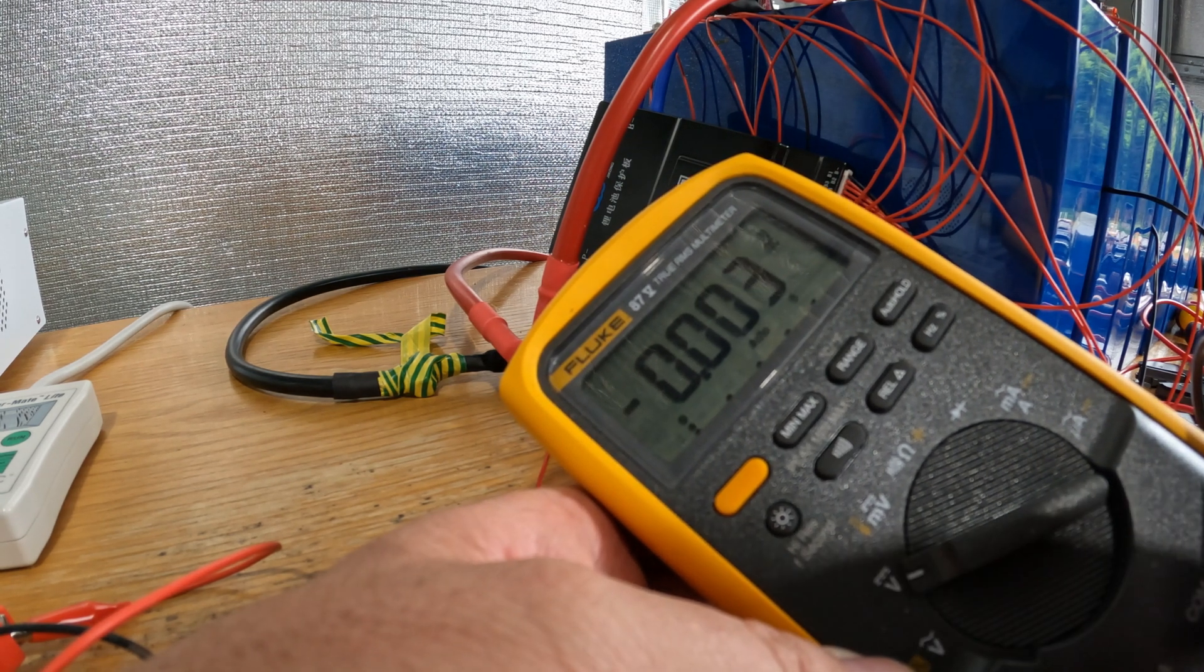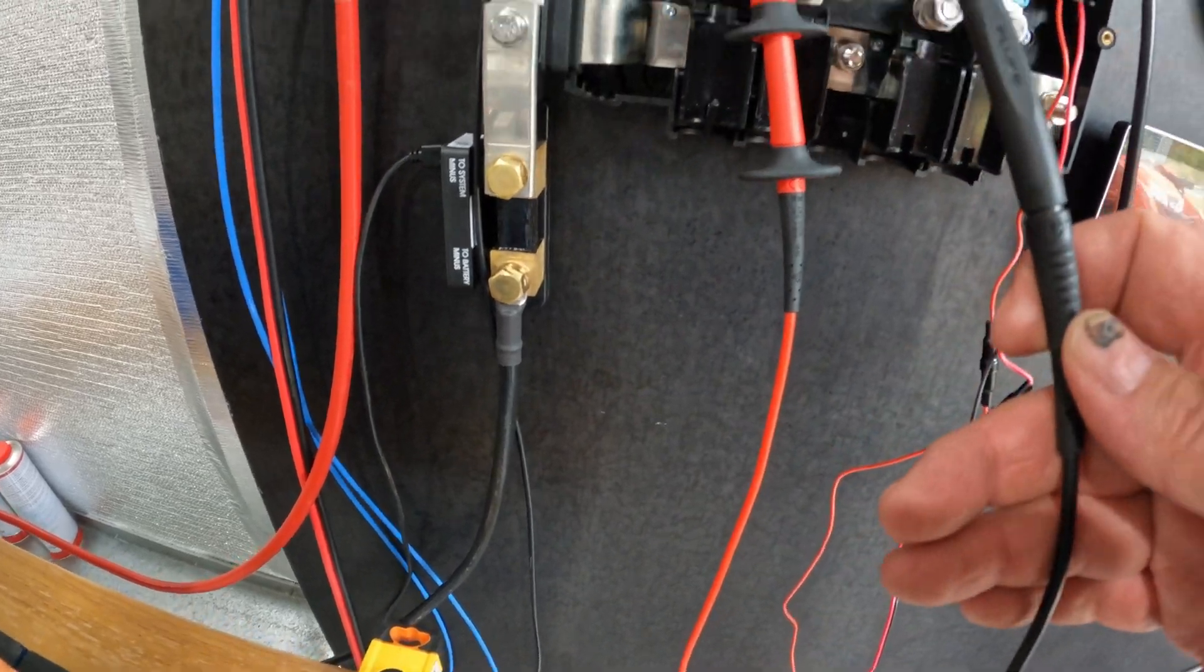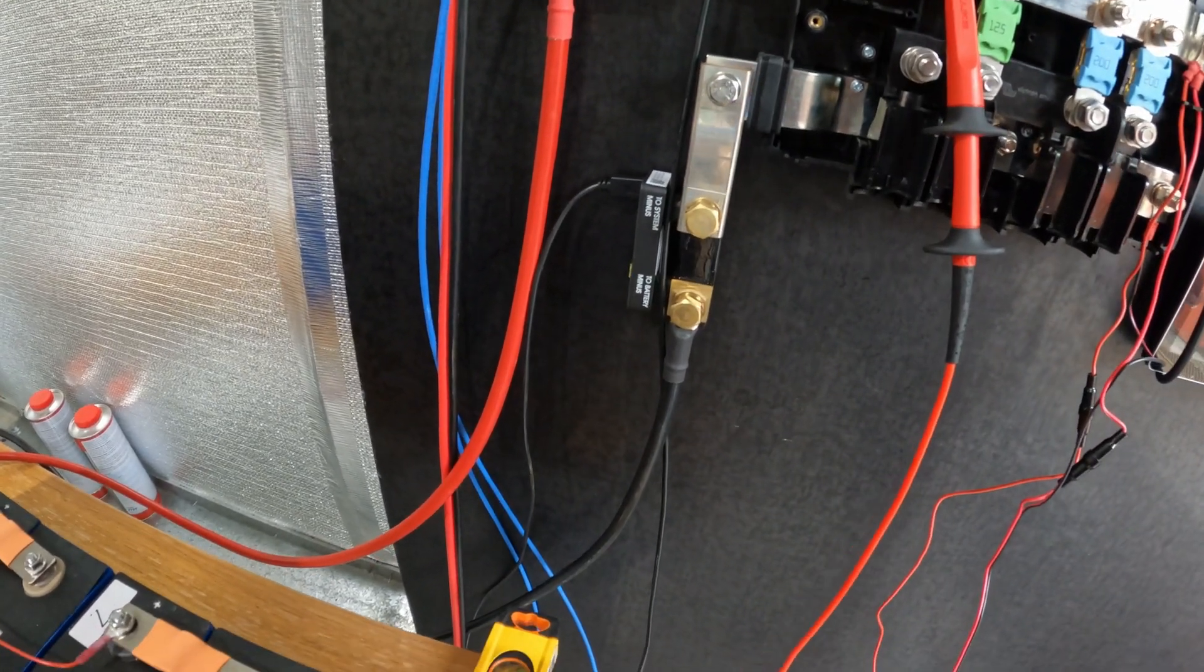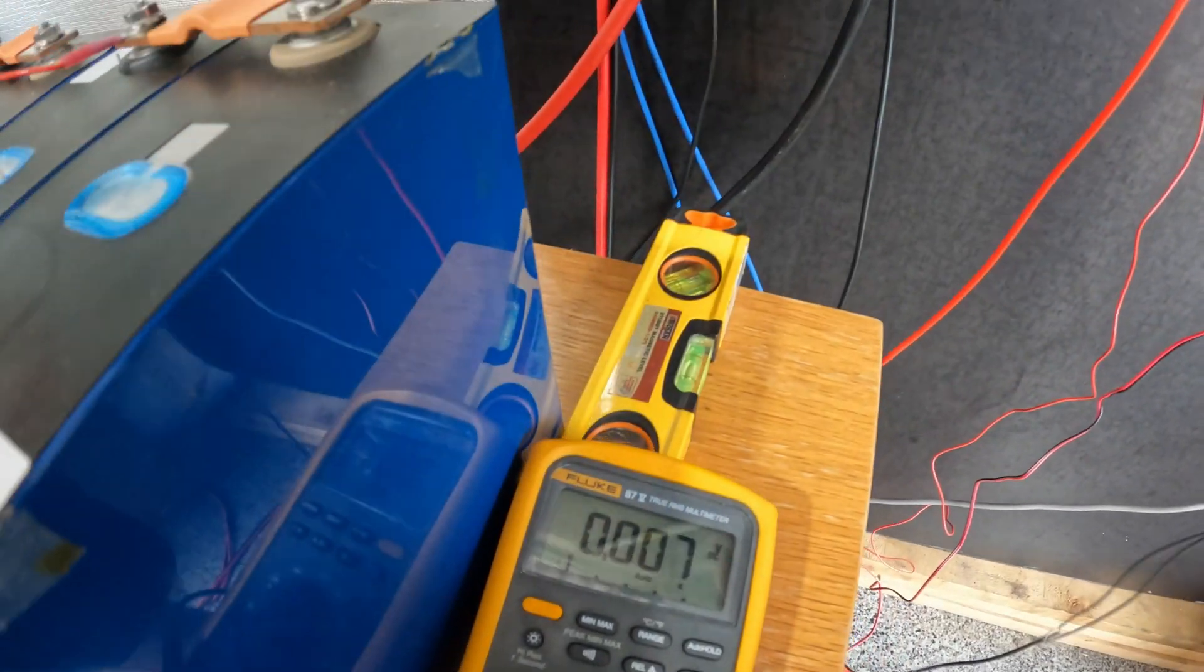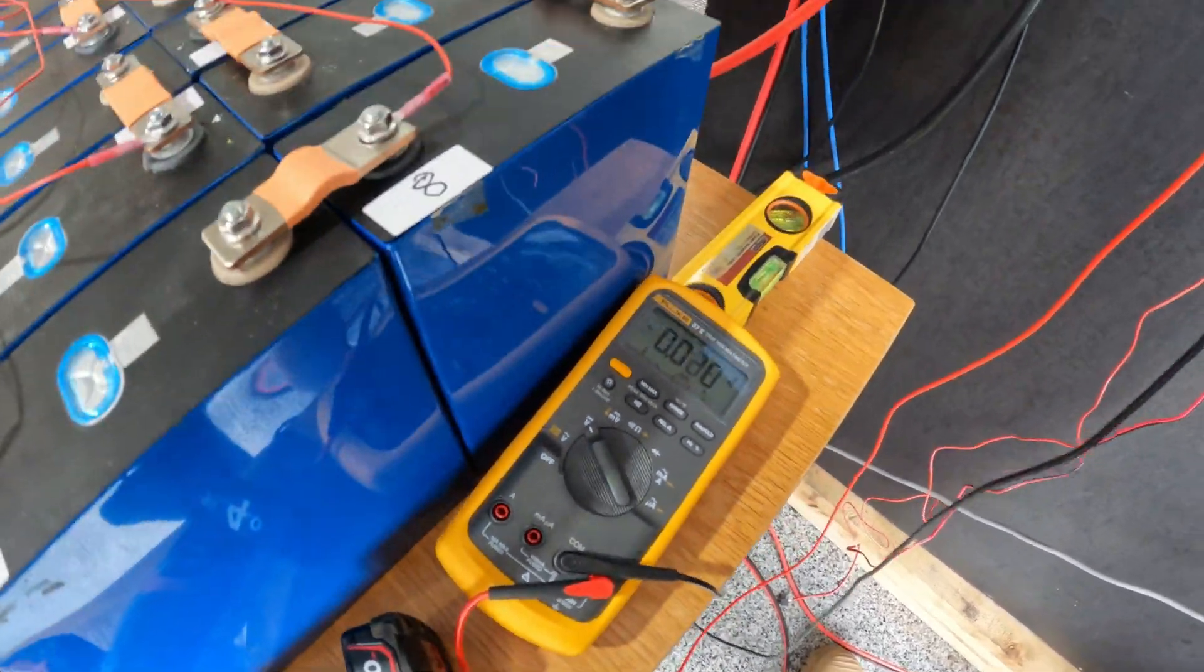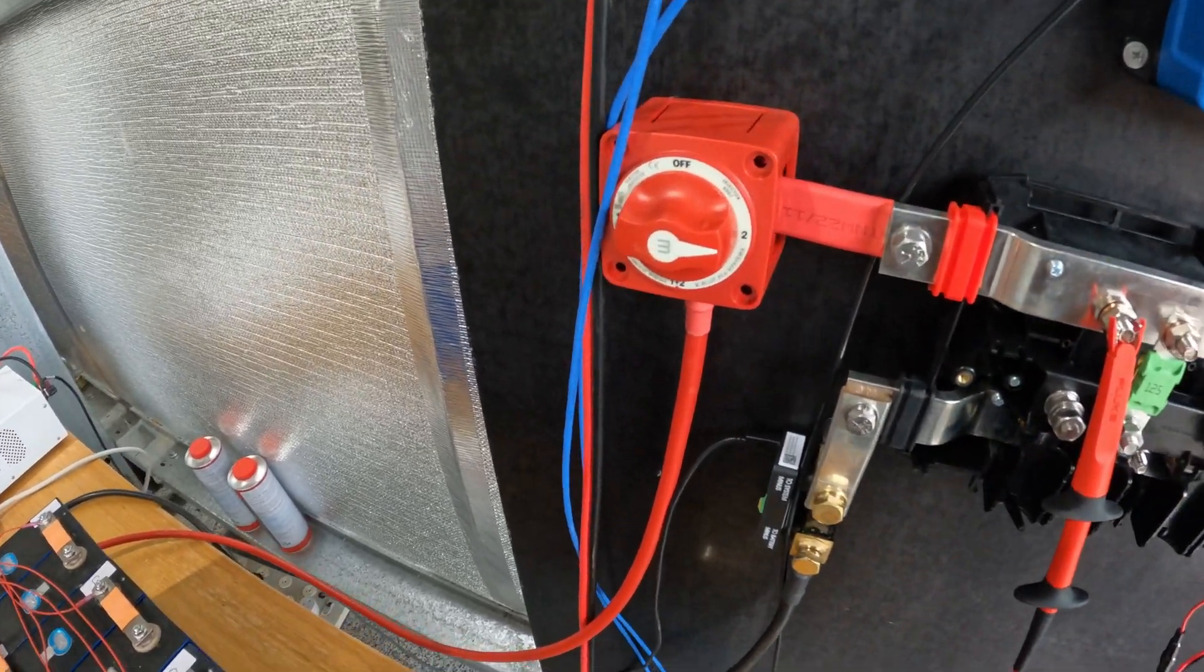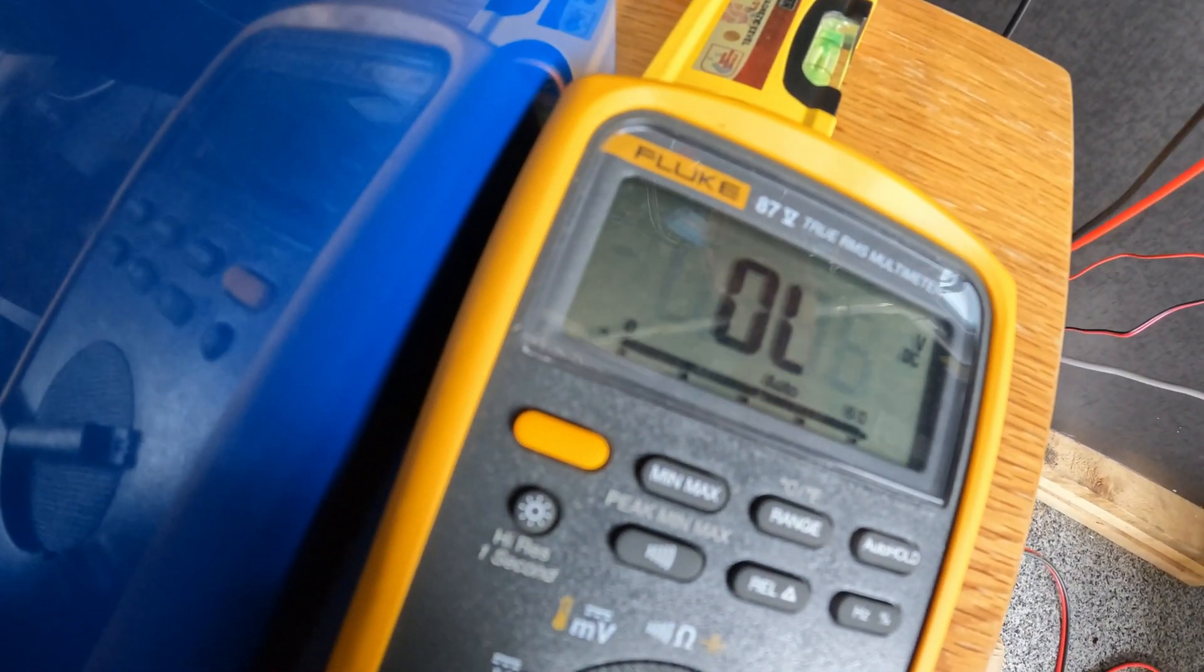53 volts for that, so there we go, we're activated. Still isolated at the bus bar, so now it's time to go check the bus bar. I've got our negative from our battery here, positive bus bar, we are isolated with this switch, so I'm not expecting to see any voltage through here until I turn that switch. Let's flip the switch. Switch on to two, that's the terminal I'm using, and check our voltage. Back voltage 53.36.